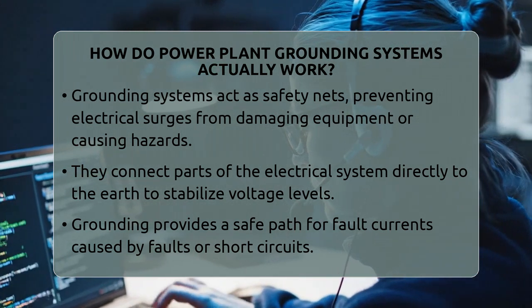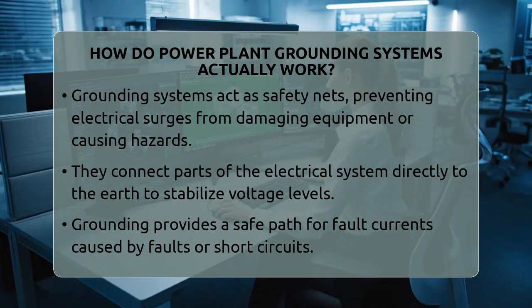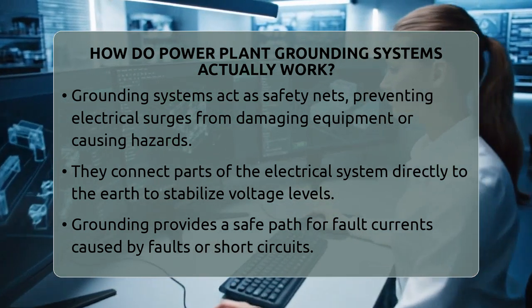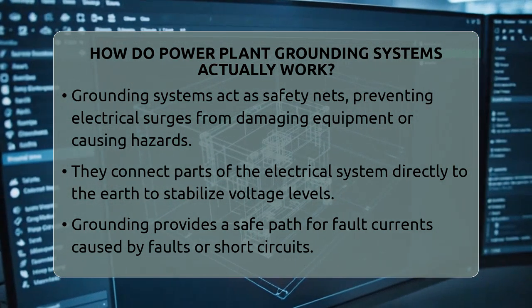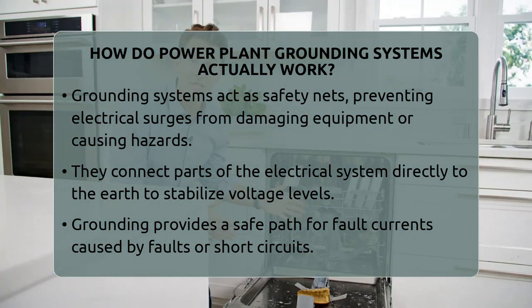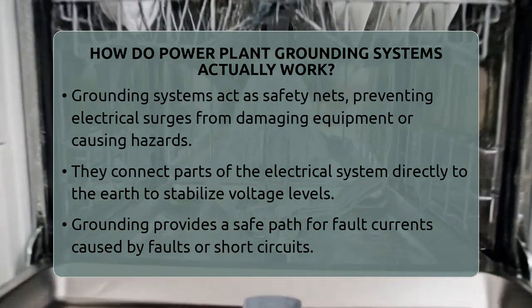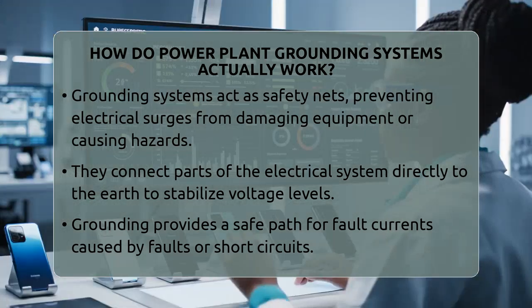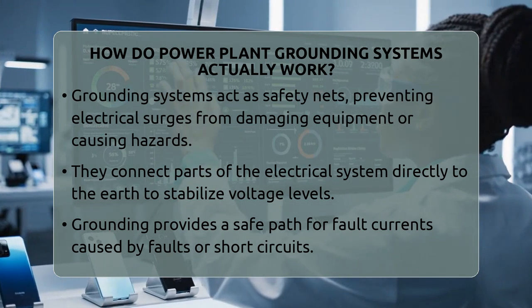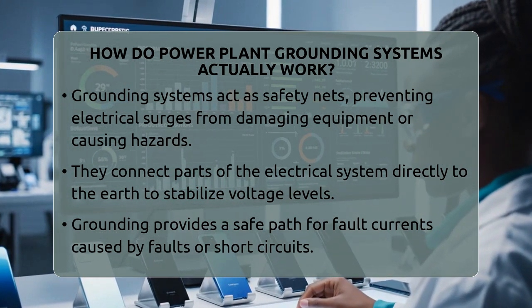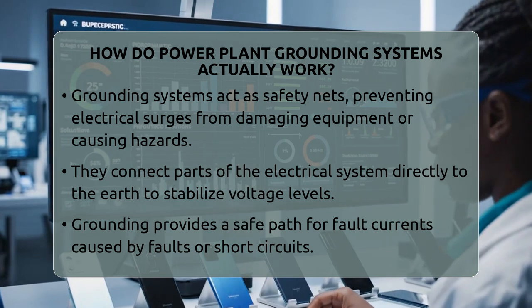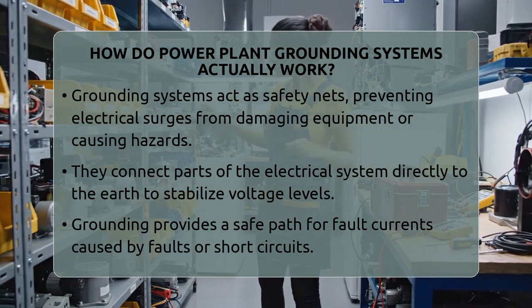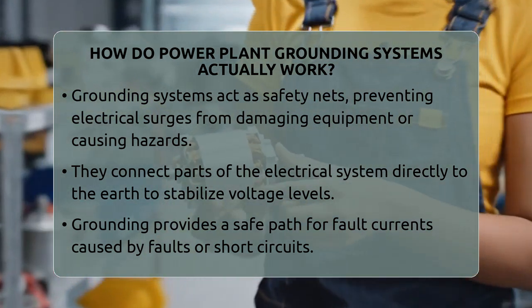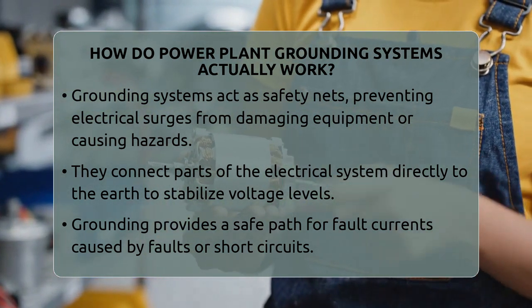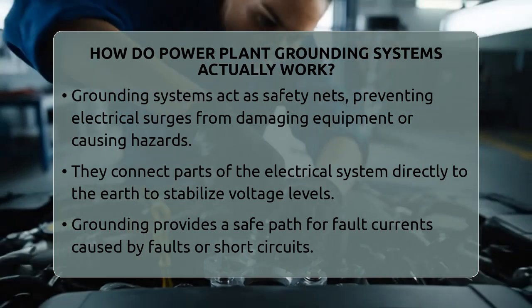When you think about power plants, renewable energy sources like solar or wind farms, and how electricity gets distributed, grounding is a key part of the puzzle. So, what exactly is grounding? It's creating a direct connection between parts of the electrical system and the earth. This connection helps stabilize voltage levels so that they don't fluctuate wildly. It also provides a safe path for fault currents, those unexpected surges caused by faults or short circuits, to flow back to the source.